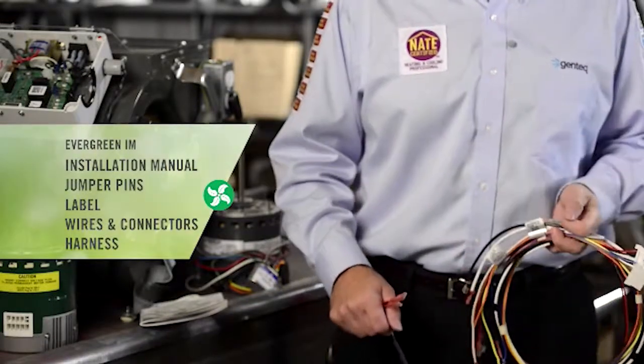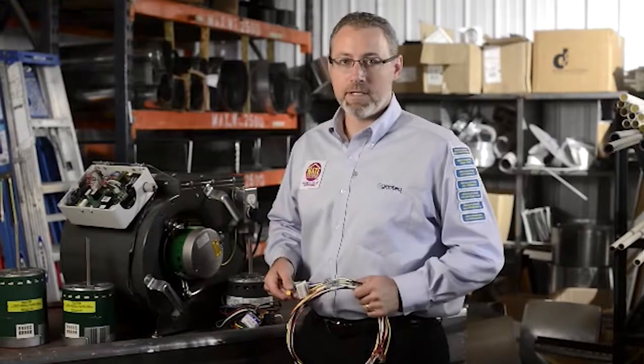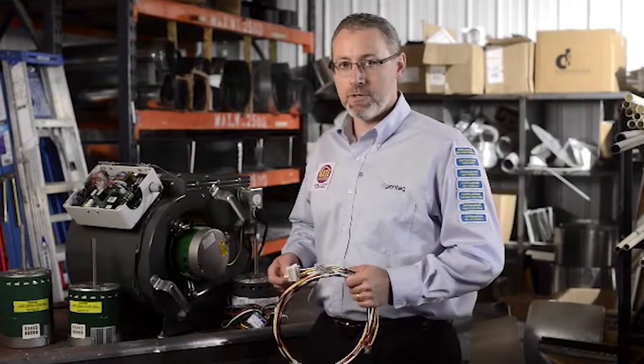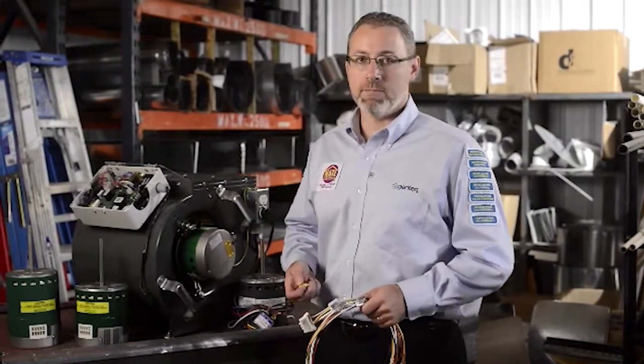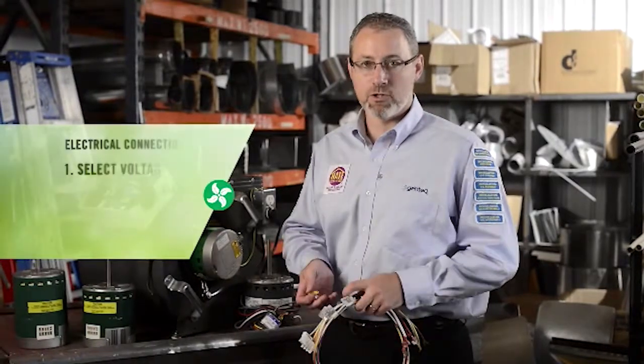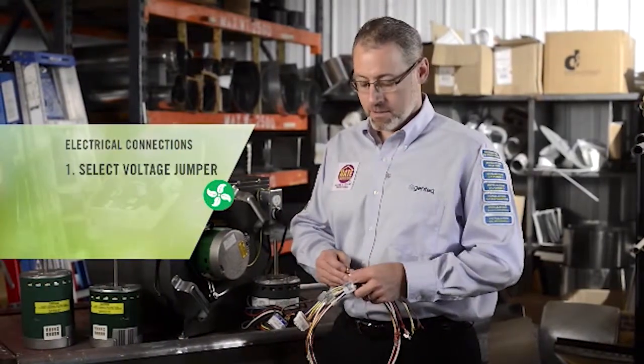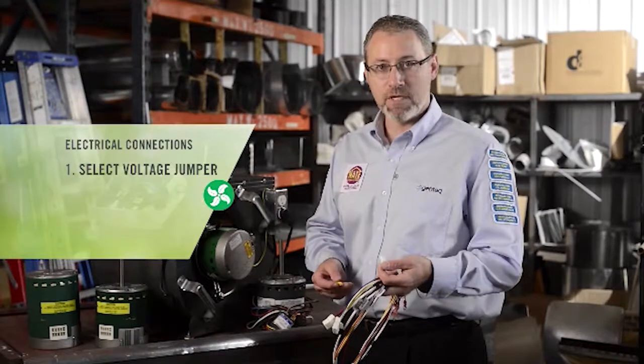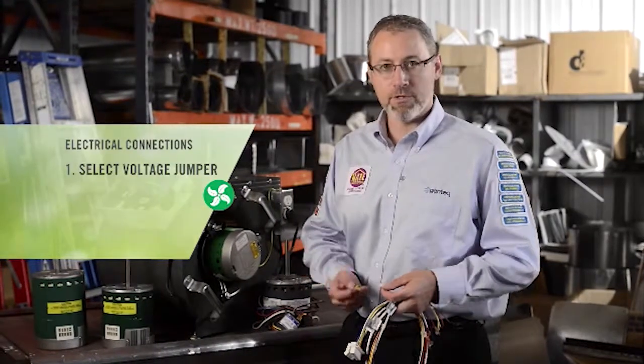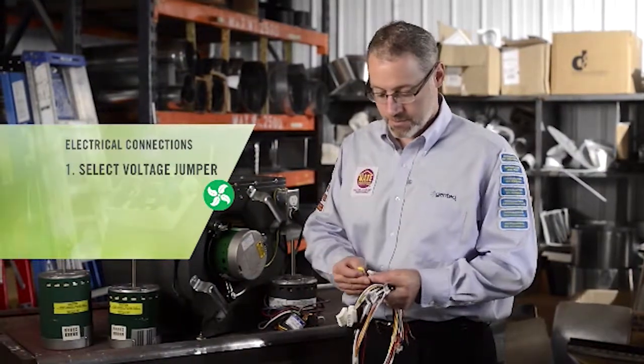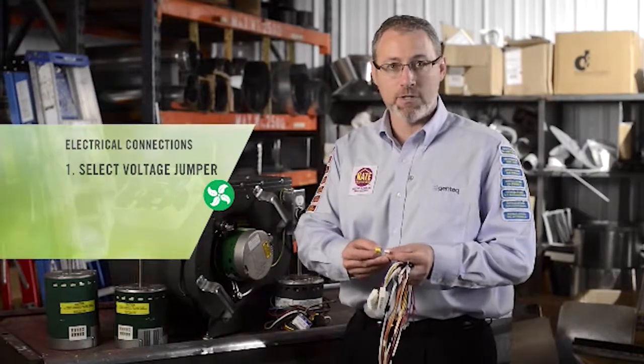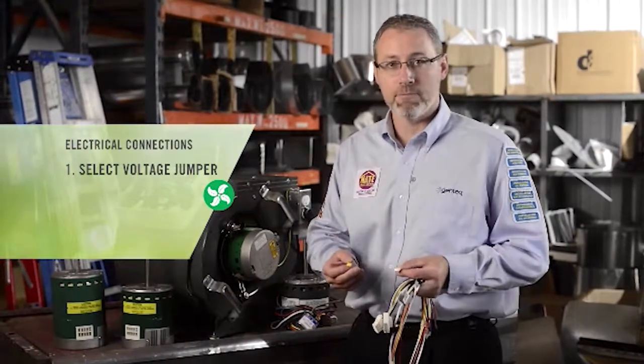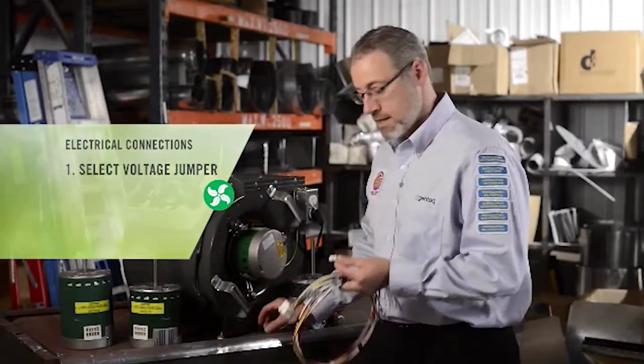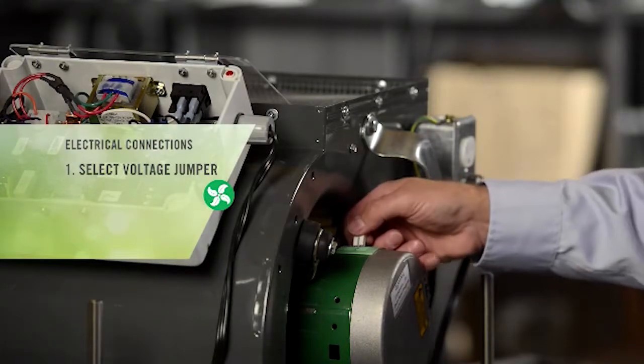Let's begin by connecting the main harness to the motor. Before we connect the harness to the motor, it's a good idea to select the voltage jumper that we're going to be using. The white jumper is used for 115 volt systems. The yellow jumper is used for 208, 230 volt systems. They are also stamped on the jumper so that you don't need to reference the manual for this information. I'm going to select the 115 volt jumper.